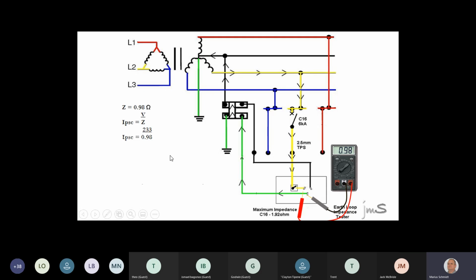So there we are. We go and we say to ourselves, will a 16 amp breaker trip if I put 237 amps through it? Yes or no? Cool. Will the breaker trip safely? In other words, can this 6 kA breaker, which will only trip between 16 amps and 6,000 amps, stop that safely? Absolutely. Because remember, only 237 amps is going to go through the breaker. If it's more than 6,000, you can stand there, I'll be gone long ago, I'll run.